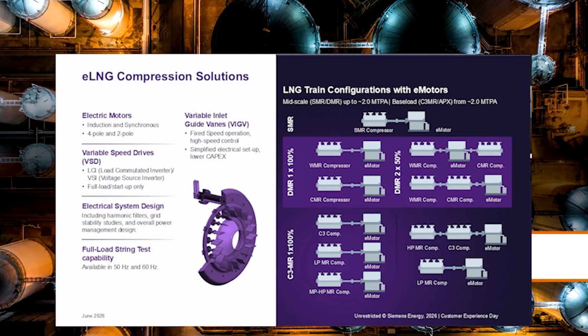That's the picture shown here, where we're basically affecting the angle of the incoming flow. This would sit at the inlet to your first impeller on the centrifugal compressor, and basically give you huge amounts of turn down capability at relatively high efficiencies in a mechanical way, as you can see, by affecting the inlet guide vane angle of the flow. And this is a contrast to the electrical way of doing process control with VFDs. So both are options. On boil-off gas compressors, we use variable inlet guide vanes routinely, and offer a fixed speed operation without the need for a VFD on the boil-off gas compressor. So there's no reason that can't be done on a mixed refrigerant as well.